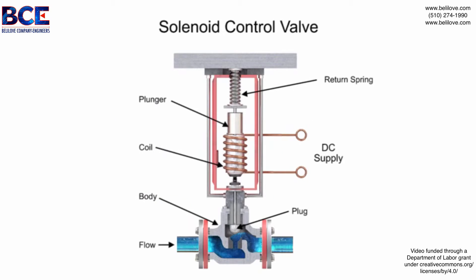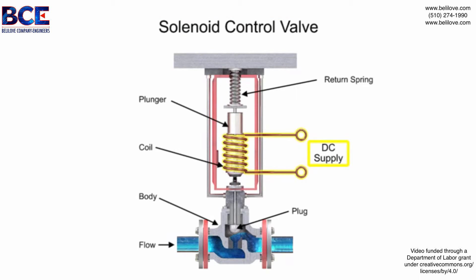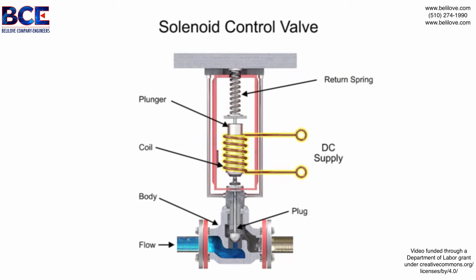For on/off control of the valve, a solenoid is used to actuate the valve to a fully closed or fully open position. Applying current to the coil generates a magnetic field that moves the plunger downward against the return spring. With zero current applied to the coil, the spring pulls the plunger upwards to the fully open position for a normally open state control valve.